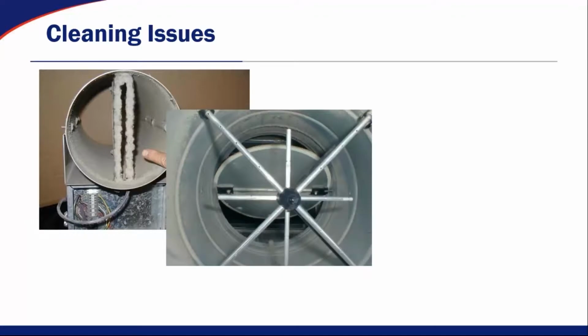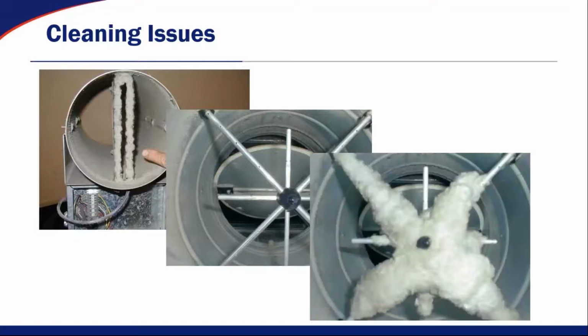so you're not going to be able to maintain your pressurization inside that space. Now, if we look to a different environment, this is a clean flow sensor inside of a patient room in a hospital. This is the same flow sensor after about 9 months of patients coming in and out of that room, the staff changing the bedding in that room and having visitors come in with dirt from outside the building. Obviously, when somebody visits somebody in the hospital, they're not making them take a shower and change into clean scrubs. So people are bringing in all that dirt from the outside world, and it goes through the exhaust ductwork or the return ductwork. And again, in this particular case, after about 9 months, that flow sensor was completely clogged up, which meant that patient room was negative when it was supposed to be neutral. Not only are you wasting energy, but you're robbing air from somewhere else in the building.